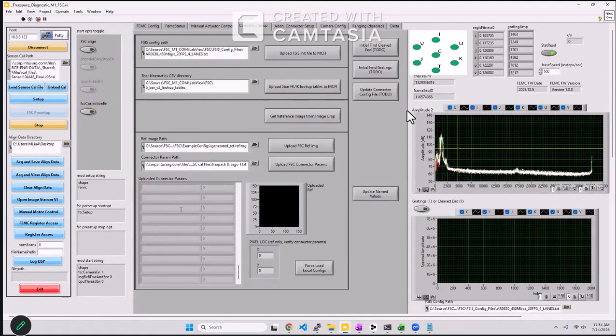A couple other things. Sorry, go ahead. And you need to have a reference image also because for every new sensing sensor that you're going to be putting, and also for the active alignment, right? Are you using the reference image for the active alignment? No. What do you mean by active alignment? Because I think this is a term that gets muddled a little bit. We have initial alignment, and then we have active alignment. Initial alignment is when we just put a catheter on, we don't have shape yet, and then we get shape. And then there's the active alignment part, which is just to get rid of the thermal drift.